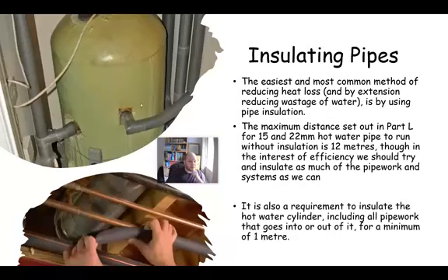Do you know what I mean? If you've replaced that cylinder and you're insulating the pipework, you're not going to rip out the whole wall to put in just an extra 500mm of insulation. You're going to just insulate it for at least 1 metre, or to the point it becomes inaccessible.